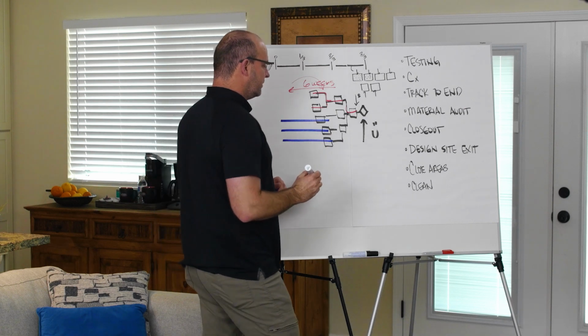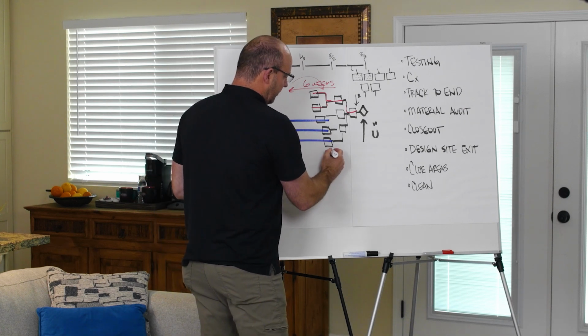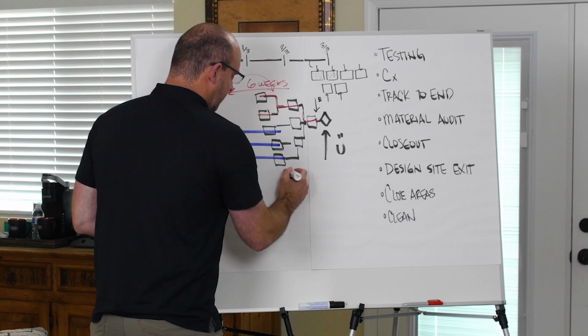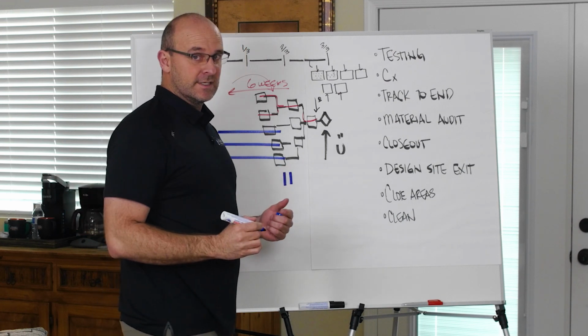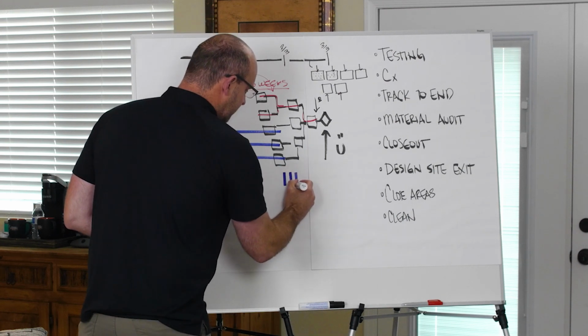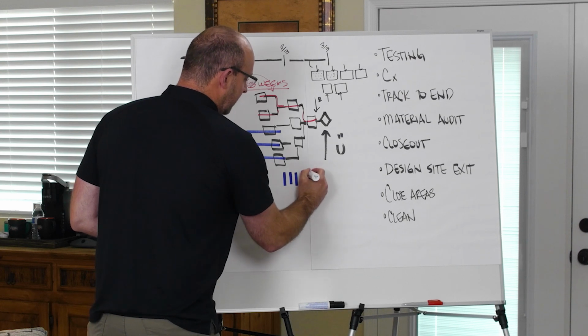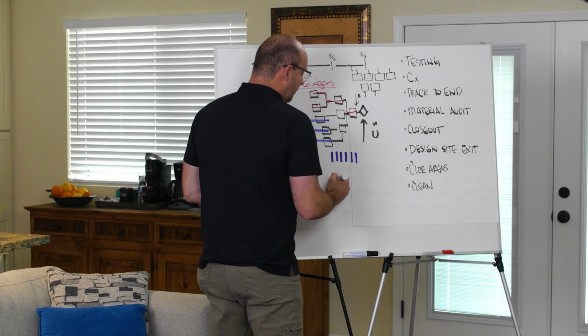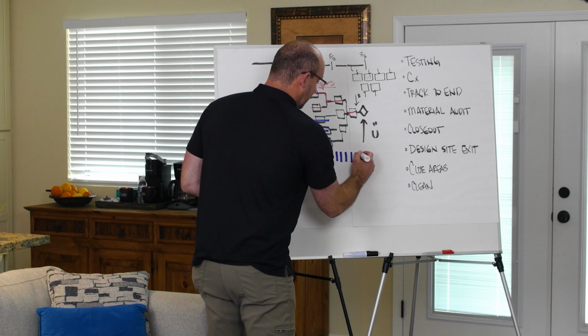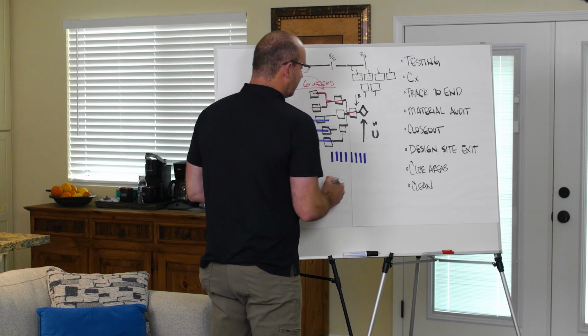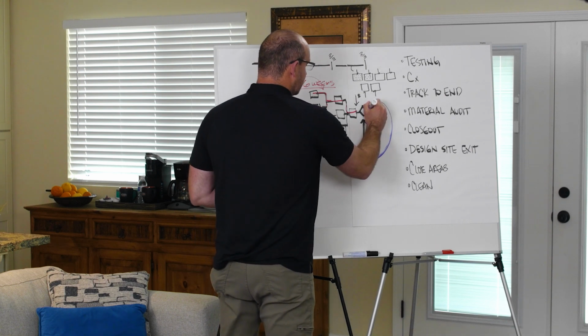They have to converge to allow you to do your pre-functional checklist, your hooking up of the dry side, wet side power communications, your point-to-point, your test and balance, your integration with the fire alarm, your functional performance testing, and your overall commissioning, and then your flush, so that you can get over here to this end milestone.